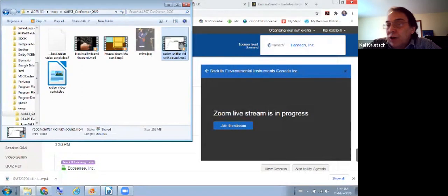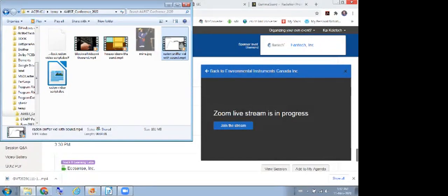Okay. It's not intended for legal measurements like real estate transactions and stuff like that. It's just to help you do the mitigation. So we don't really worry too much about absolute accuracy and traceability. I mean, it's going to be accurate to within plus or minus 10-20%, but we're not too worried about traceability. Do you require some sort of periodic factory checks, maybe every year or every 2 years?